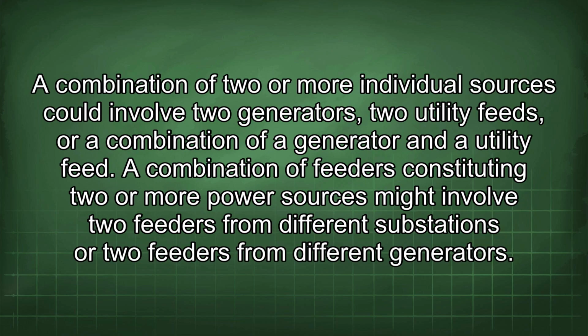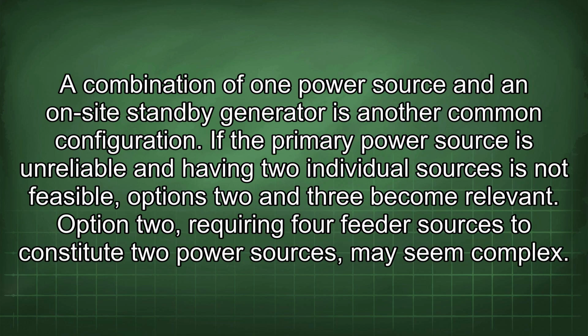A combination of two or more individual sources could involve two generators, two utility feeds, or a combination of a generator and a utility feed. A combination of feeders constituting two or more power sources might involve two feeders from different substations or two feeders from different generators. A combination of one power source and an on-site standby generator is another common configuration.